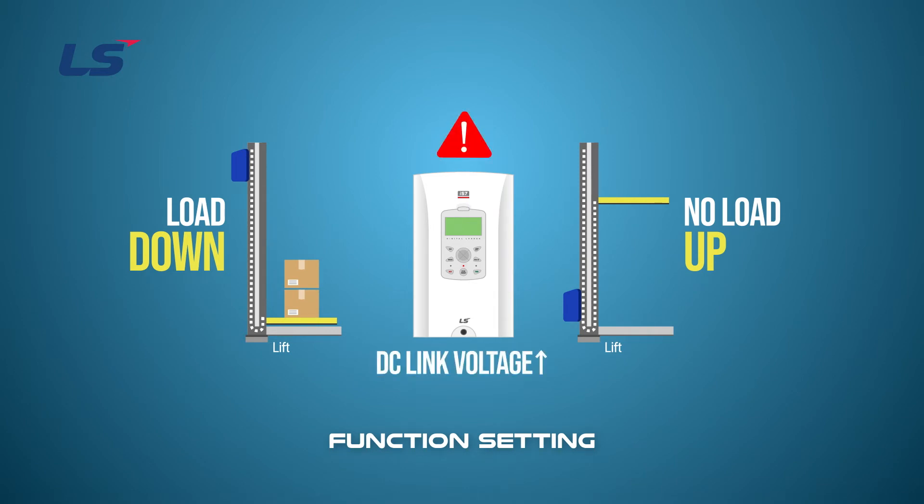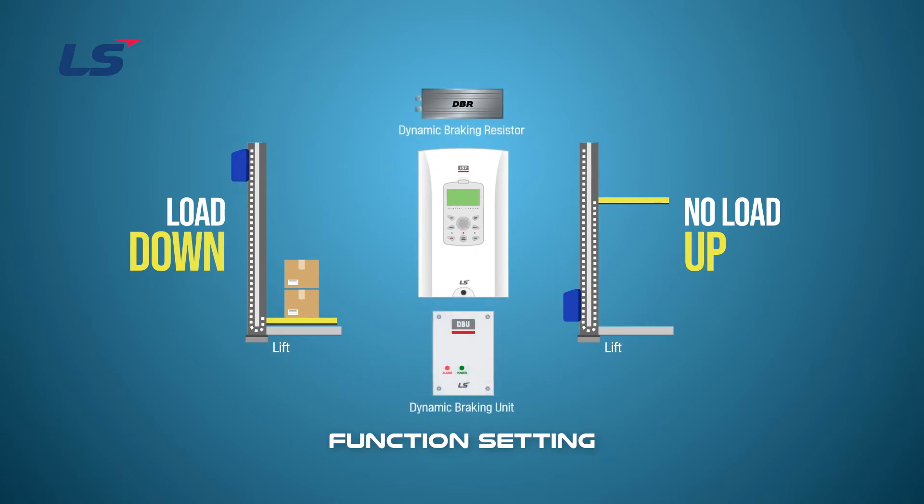Since there is a condition in which regenerative voltage is generated during lift operation moving up and down, it is recommended to install a brake resistor and a brake unit to prevent an over-voltage trip of the inverter.